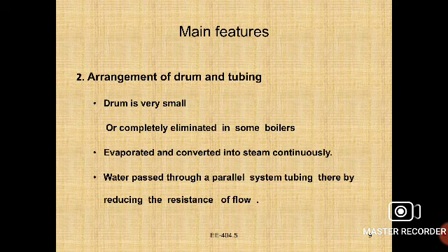The second feature is the arrangement of drum and tubing. The size of the water drum is very small, and in certain cases it is completely eliminated. Water flowing through pipe circuits is evaporated and converted into steam continuously.